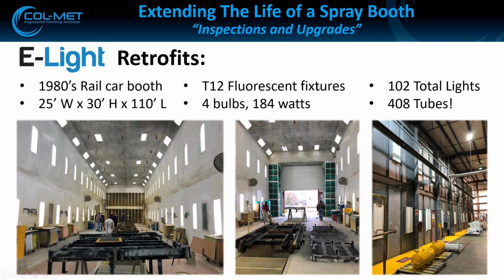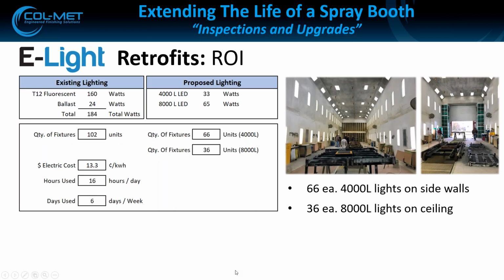Let's look at the math here, just looking at energy. If you take your 160 watts per fluorescent light, and each ballast has 24 watts, you've got to get 184 watts. Where our light fixtures, the 4000 lumen ones, are producing about the same as that T12, and they're only 33 watts. So you can see there's a substantial savings.